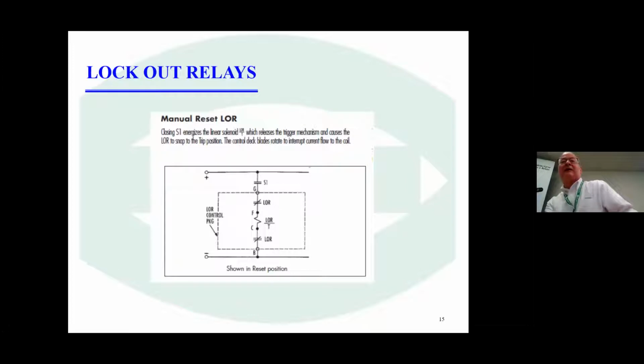And in a manual lockout relay system, the S1 is all I need to trip that coil. And you'll see what happens. When I trip the coil, I get the solenoid to operate, and then immediately the LOR contact opens and takes the voltage off of that trip coil. If you keep resetting a lockout relay into a fault, you're going to burn up that coil. And that happens quite frequently. So one of the cautions you want to make sure you have is to never reset a lockout relay multiple times into a fault until you've identified what that fault is.